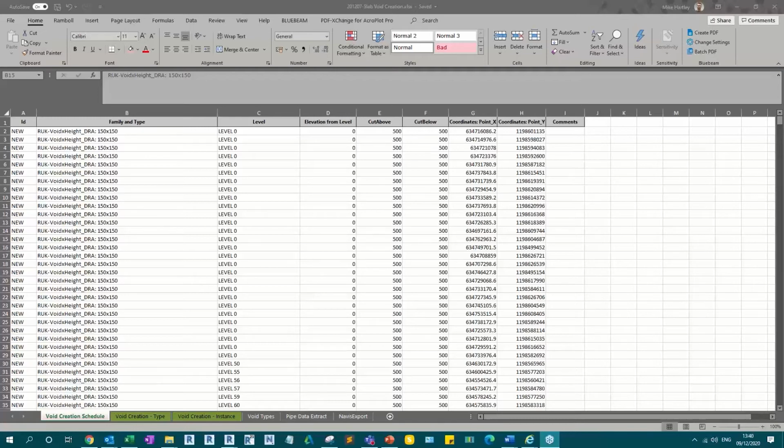In summary, in Navisworks we run our clash detection and do an extraction from Navisworks. All I'm interested in from that extraction for this process is the element ID, the same element ID that you get from a Revit model. With that, I then use BIMlink to do an extraction from the MEP model and an extraction from the structural model.